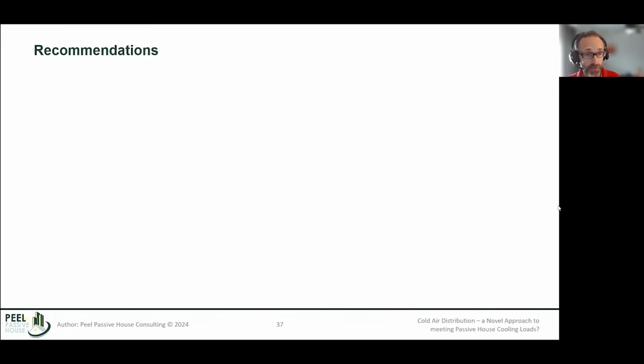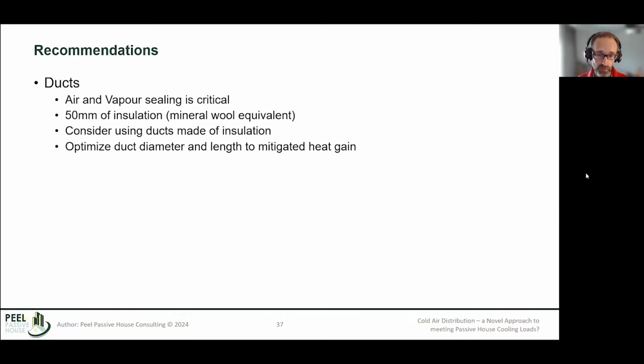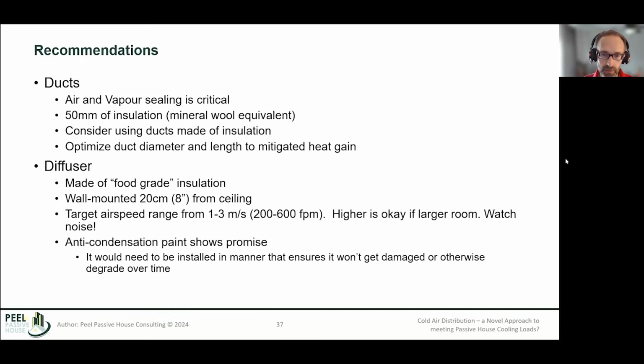Okay, so overall success for the factors we investigated. In terms of some recommendations for implementation: for ducts, fully air and vapor sealing is critical to avoiding condensation. The recommendation is 50 mm or 2 inches of mineral wool equivalent insulation. You could consider using ducts that are made of insulation, rather than insulating metal ducts or other types of ducts. And to avoid a big temperature gain between the coil and the diffuser, we want to optimize the diameter of the duct and try to reduce the length as much as possible so we get less heat gain.